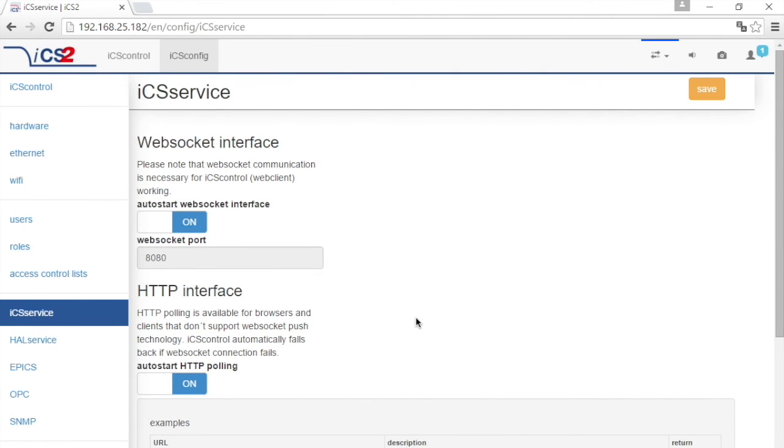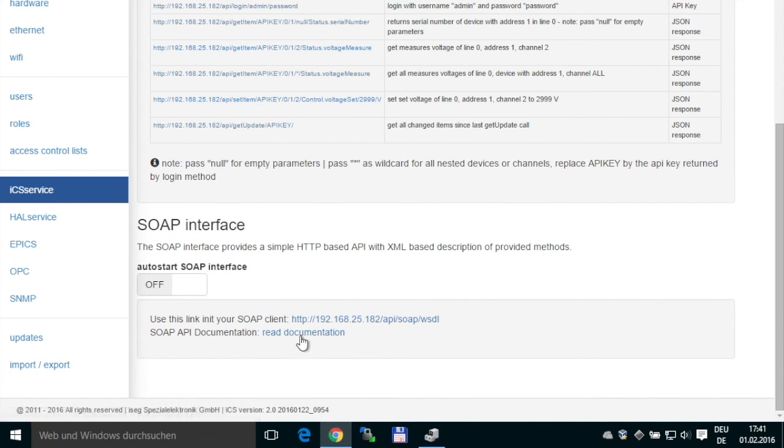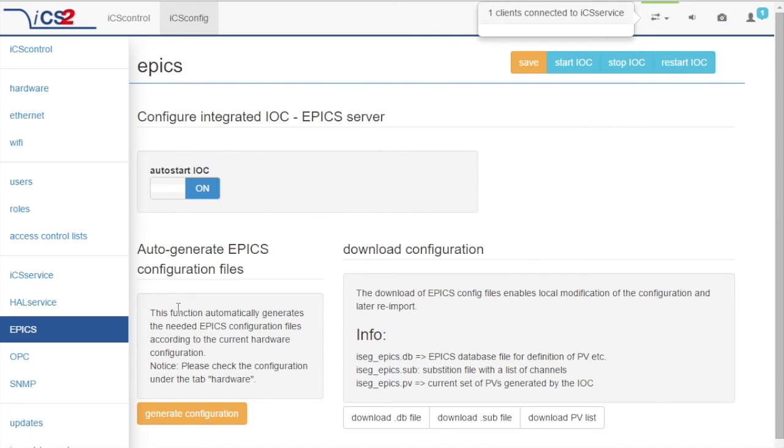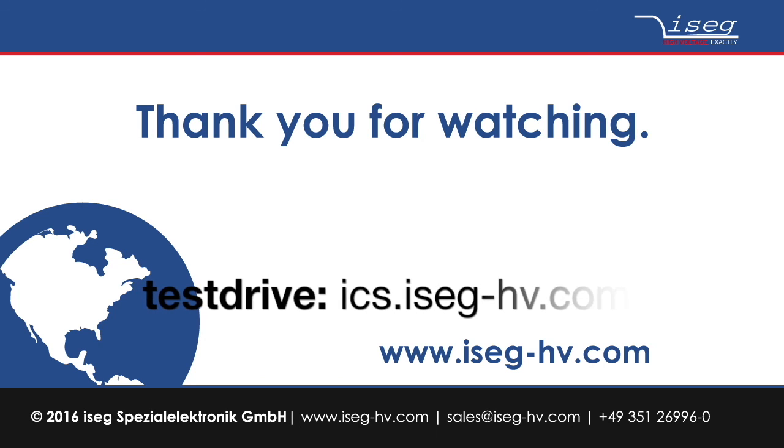For the implementation of the high voltage system into already existing facility system control software, the ICS2 offers several software services such as WebSocket-based or HTTP-based interfaces, a SOAP interface, an EPICS IOC, an OPC UA server, or an SNMP interface. By the use of one of the integrated application programming interfaces, it is easily possible to integrate the control and monitoring of iseg multi-channel high voltage modules into almost any external control software.